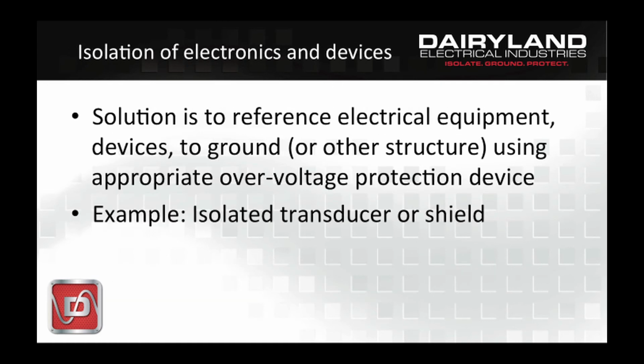The solution is to reference electrical equipment or devices to ground or to other structures with an appropriate overvoltage protection device. We don't want to let the electrical equipment float and rise to a very high voltage where it could possibly fail. So think of as an example a transducer on a pipeline. If the transducer or its shield were isolated and that isolation point were left open with no further protection, the pipeline could rise in voltage and fail the transducer. So bonding across with an appropriate overvoltage protection device would alleviate that.